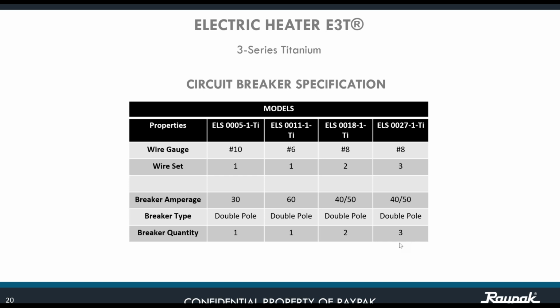There is a key element on this electrical connection, and it is the wire gauge. Just keep in mind that you need to have the proper wire size for the specific unit. For example, for the 5.5 is number 10, for the 11 is number 6, for the 18 is number 8, and for the 27 is number 8. And we have a number of wire sets that is specific for every unit. For the 5.5 is 1, for the 11 is 1, for the 18 is 2, and for the 27 is 3. When we say wire set, we are referring to a set of 3 cables: L1, L2, and ground. Just keep in mind that a wire set is going to be comprised of 3 cables.